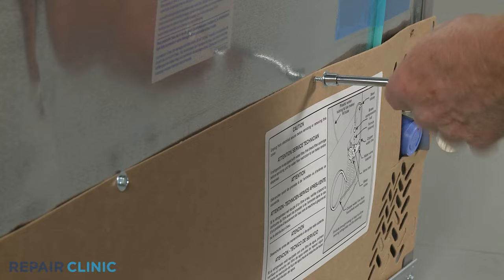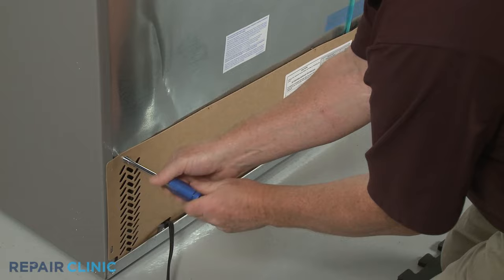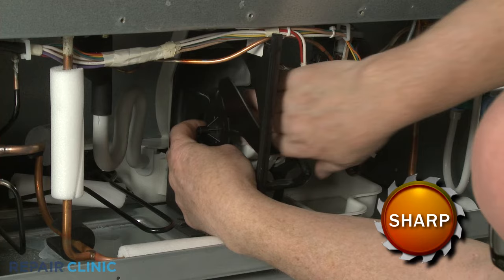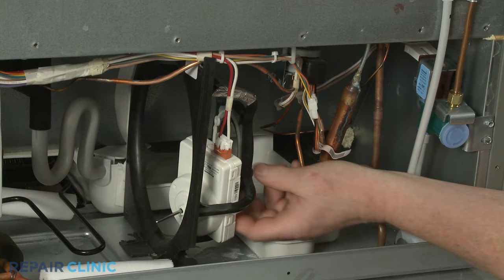Unthread the screws securing the access panel and set the panel aside. Reach in and push the condenser fan blade off of the motor shaft. Unthread any mounting screws securing the fan motor to a mounting bracket. Disconnect the wire connector to fully remove the old motor.